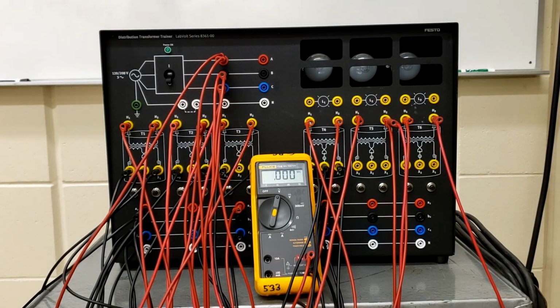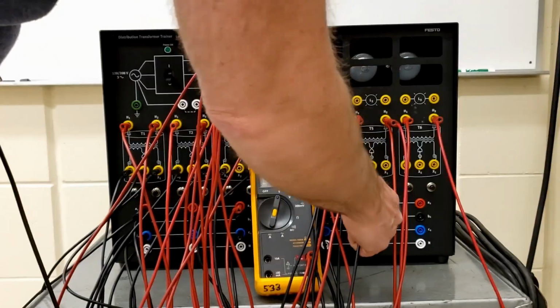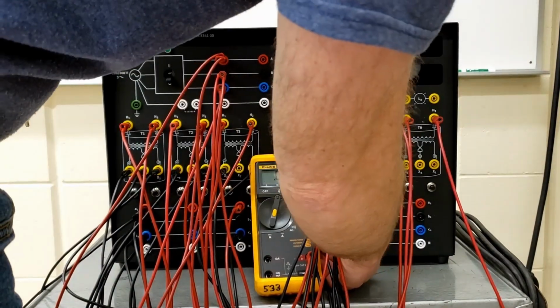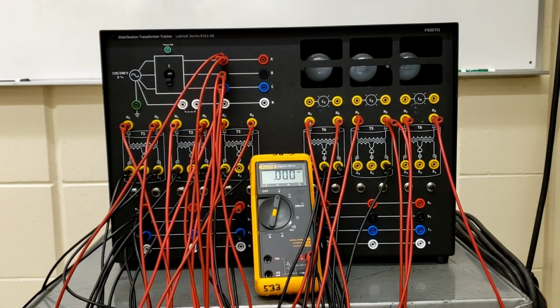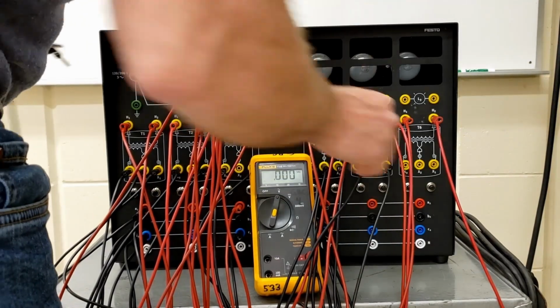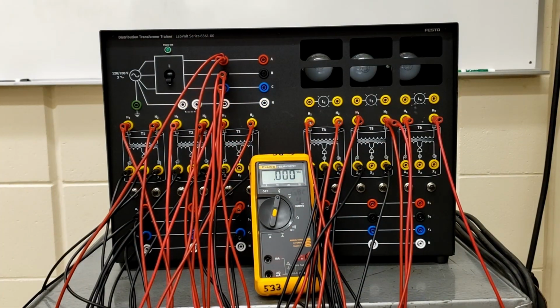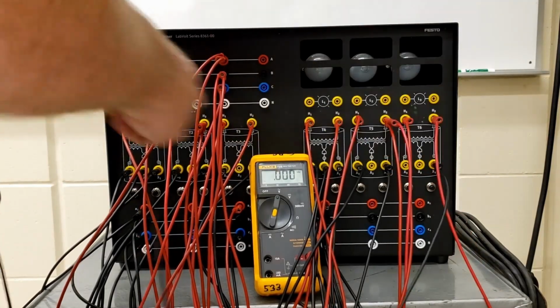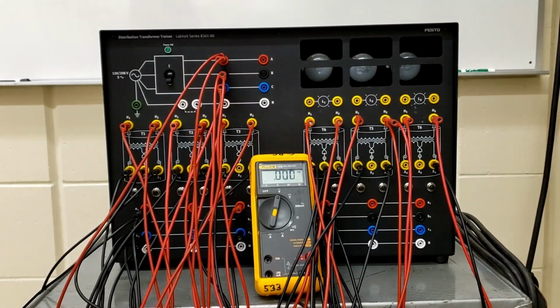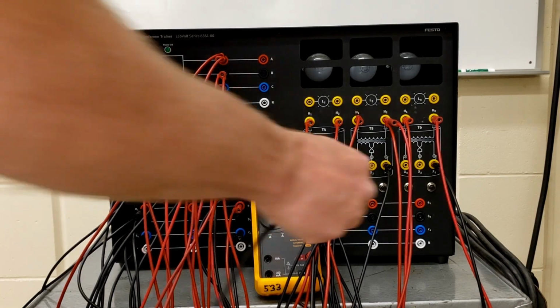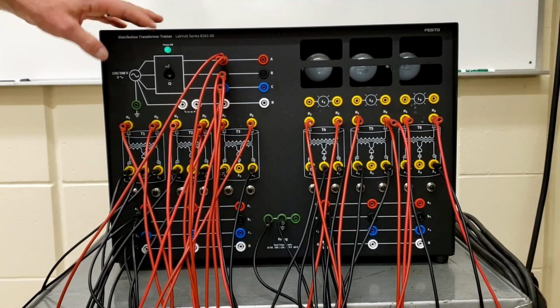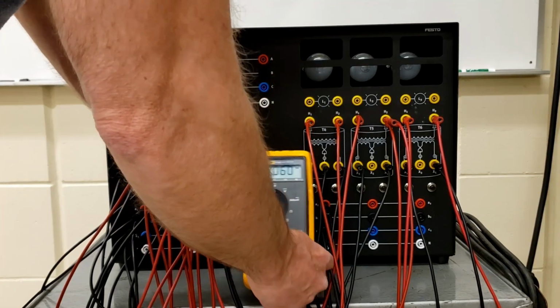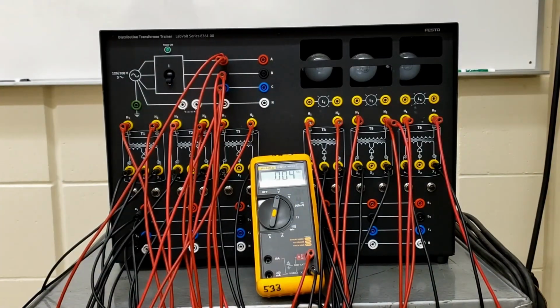Okay, second transformer we have X1 feeding the C phase. So X1 feeding the C phase. X3 is going to B phase. Okay, and then on our third transformer, X1 is going to A. Okay, and we've got X3 going to C. Okay. Excellent. Let's make sure that everything holds first. Looks good.